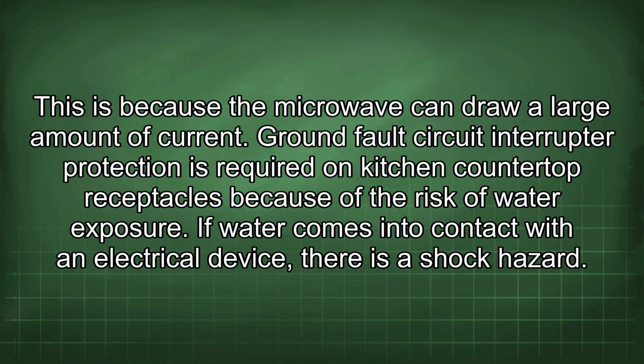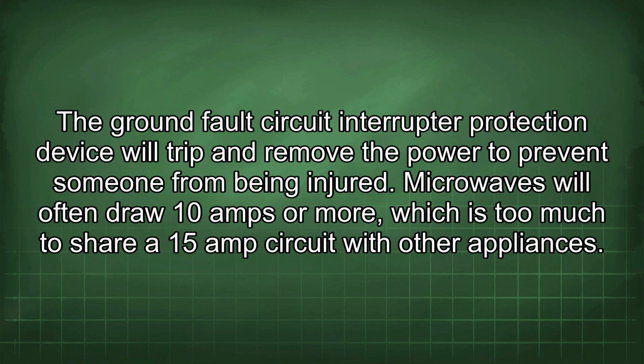This is because the microwave can draw a large amount of current. Ground fault circuit interrupter protection is required on kitchen countertop receptacles because of the risk of water exposure. If water comes into contact with an electrical device, there is a shock hazard. The ground fault circuit interrupter protection device will trip and remove the power to prevent someone from being injured. Microwaves will often draw 10 amps or more, which is too much to share a 15-amp circuit with other appliances.